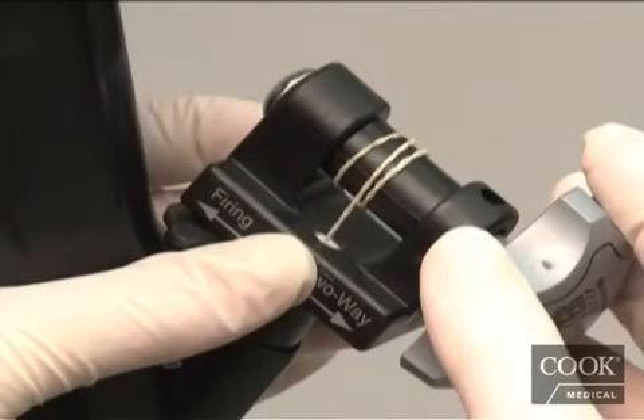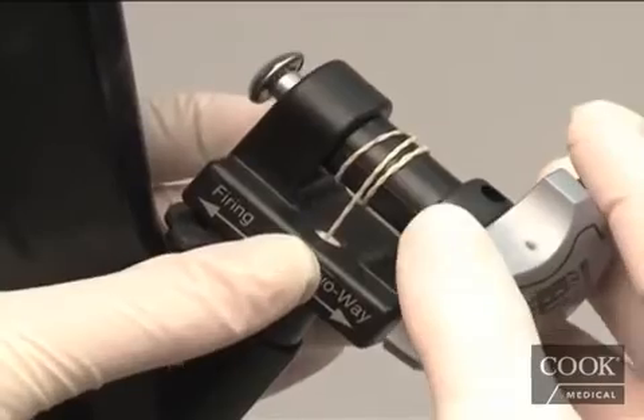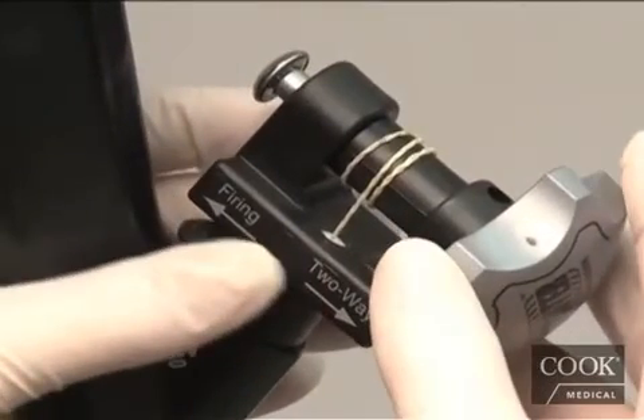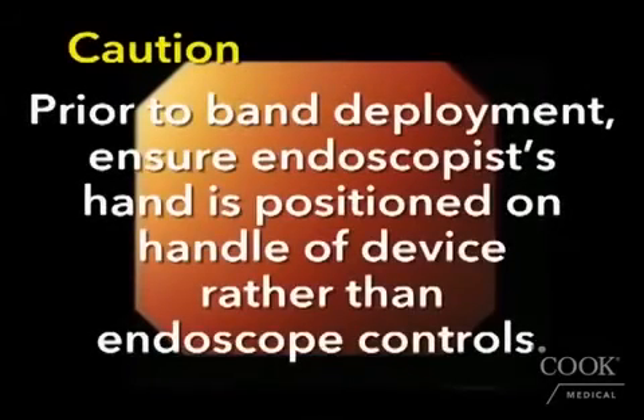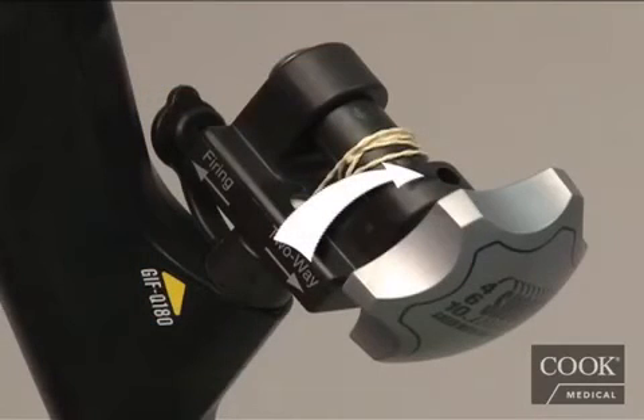With the handle in the two-way position, introduce the endoscope into the esophagus. After intubation, place the handle in the firing position. Visualize selected varix and aspirate into the barrel. Caution: prior to band deployment, ensure that the endoscopist's hand is positioned on the handle of the device rather than endoscope controls. Maintain suction and deploy band by rotating the handle clockwise until band release is felt, indicating deployment.